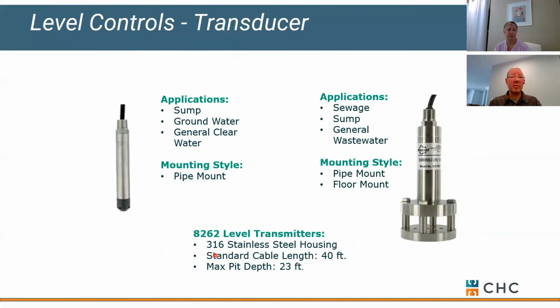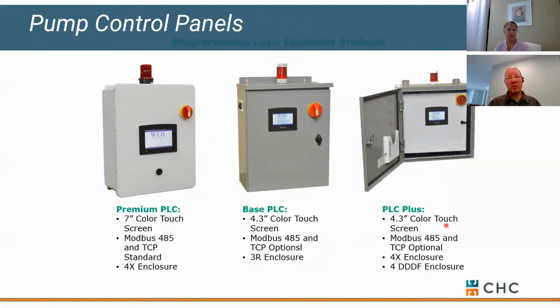Another option that we're seeing picking up quite a bit of action is using a transducer instead of floats. Now this transducer can attach to the discharge pipe. It can also sit at the bottom of your basin, and all it's doing is picking up the water level inside your basin. An advantage of that is you can sit outside at a programmable control panel, and based on the water height in the basin, you can tell the pumps when to turn on and off. You can tell the high water alarm when you want that triggered. It just makes life easy. You're not pulling floats in or out to adjust them. You can do it all at the control panel.